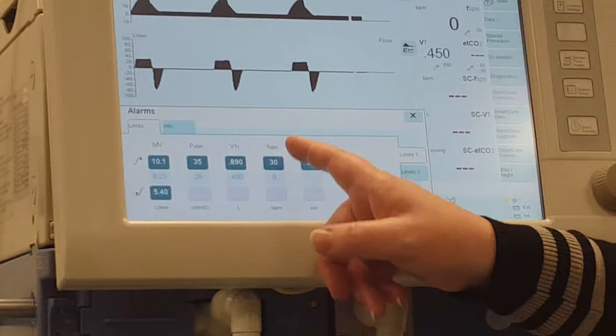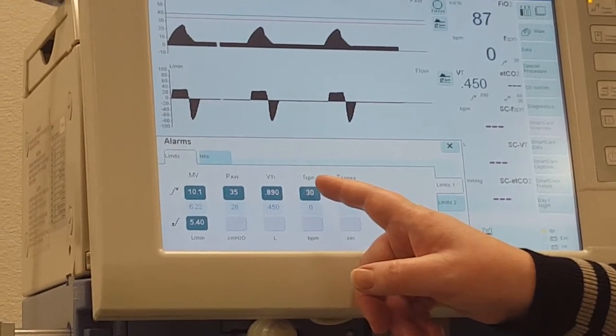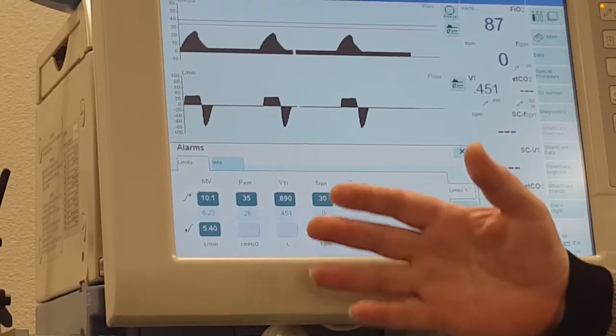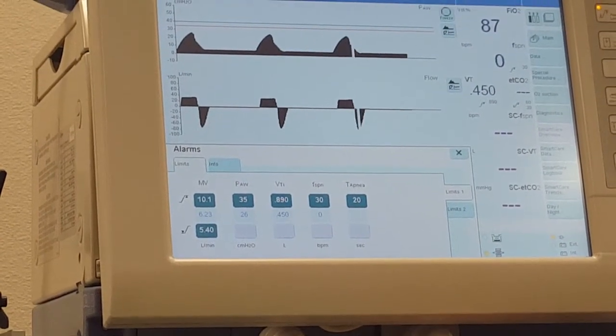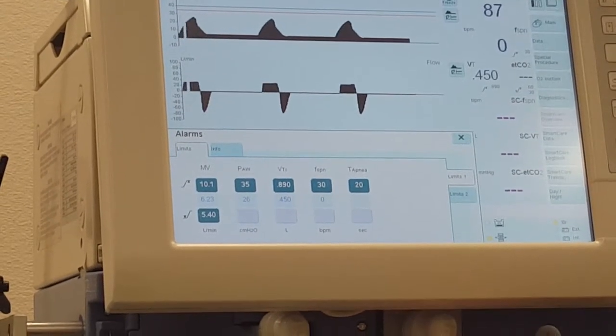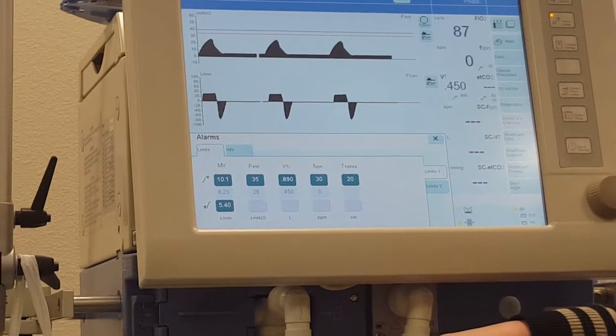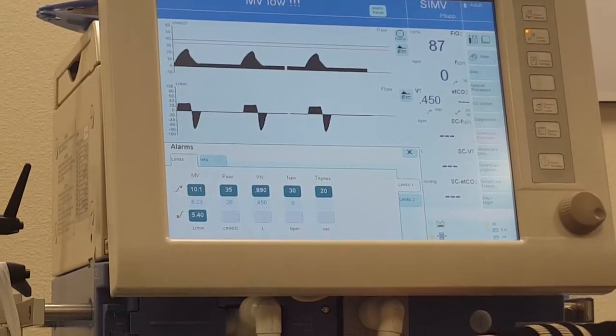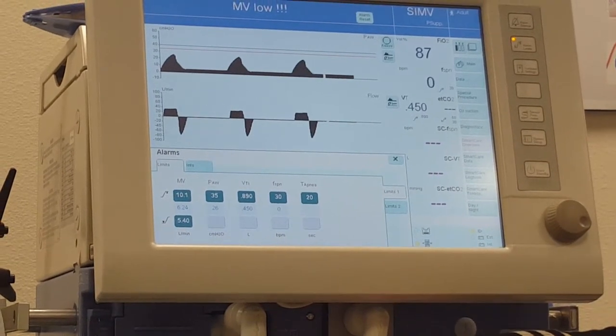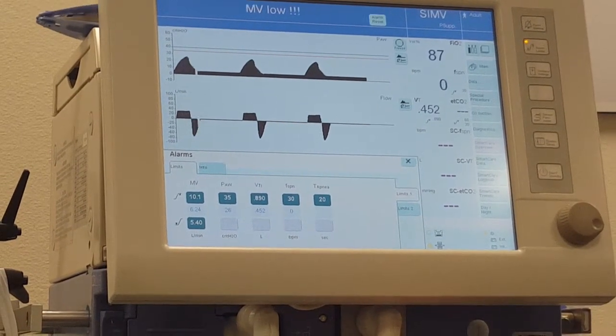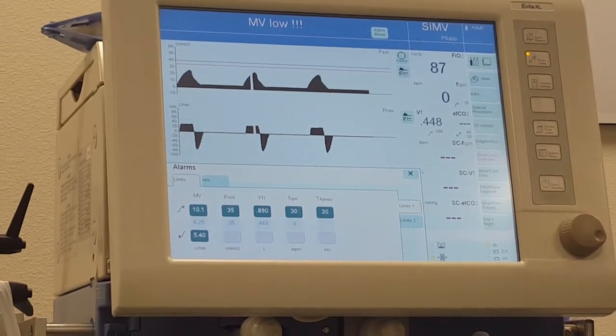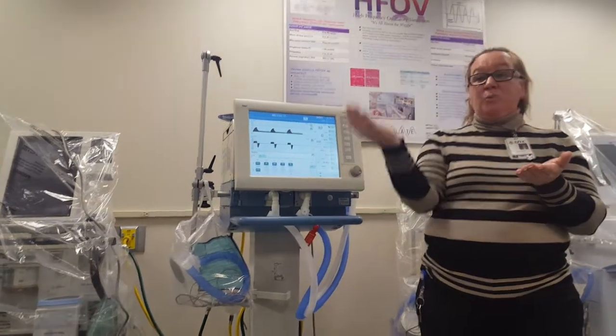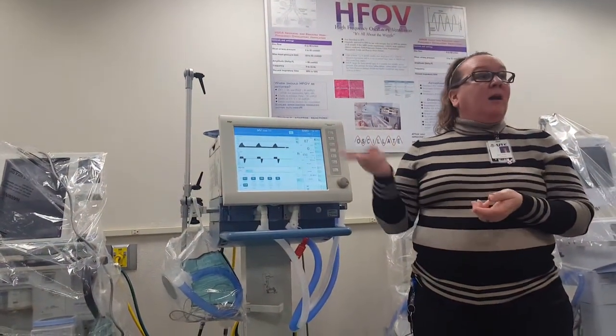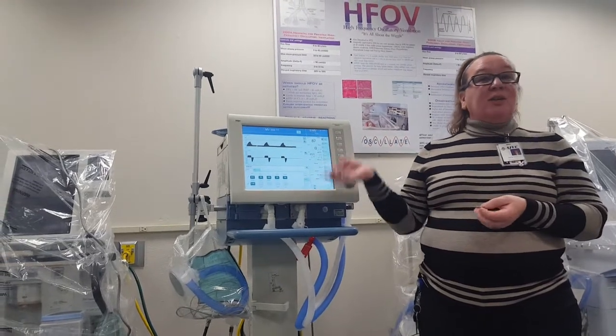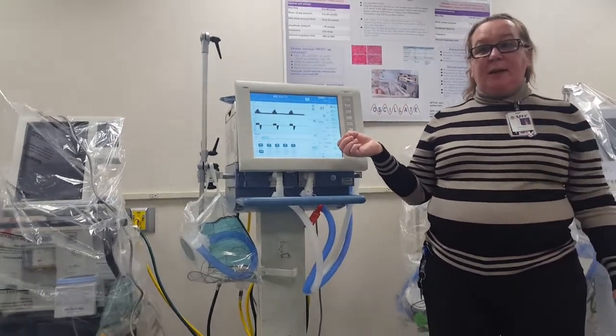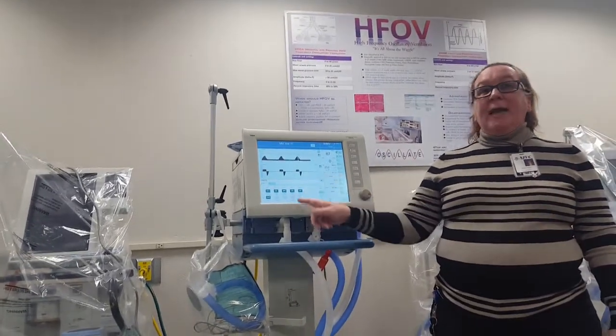The other thing about the alarms is this last one, it's called F, like frequency, SPN, which stands for spontaneous. So this is the spontaneous frequency alarm. Normally, you're going to learn that on every other ventilator, you set your high respiratory rate to 10 above whatever you're doing. So if my respiratory rate's at 12, 10 above would be 22. So that way my set rate plus my spontaneous rate, if the two of them are more than 22, it would alarm. So if it goes more than 10 above. On the DRAGER, the only thing it's taking into consideration is the spontaneous rate. It's not even looking at the base rate. So this needs to be set on 10.